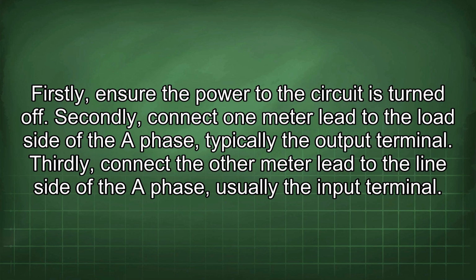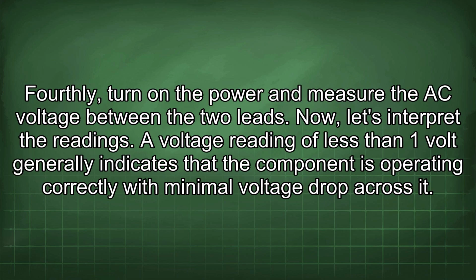Secondly, connect one meter lead to the load side of the A phase, typically the output terminal. Thirdly, connect the other meter lead to the line side of the A phase, usually the input terminal. Fourthly, turn on the power and measure the AC voltage between the two leads. Now, let's interpret the readings.